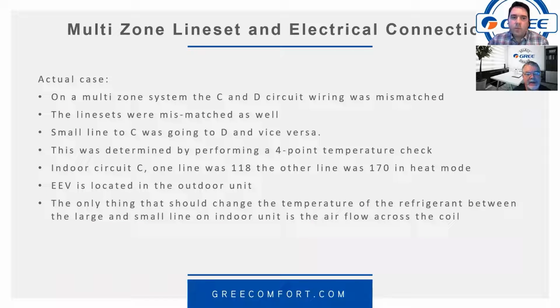This is an actual case. You just ran across this recently, right, Daniel? Yeah. So on a multi-zone system, the circuit wiring was mismatched according to which indoor unit it was going to. But not only that, the refrigerant piping was mismatched with the particular circuit that it was supposed to go to as well. So it was not only confused about which indoor unit was calling for refrigerant to be metered to it, it was also sending it through the wrong pipe to a different indoor unit. Yeah. So that can certainly cause a little confusion for the system, very confusing.